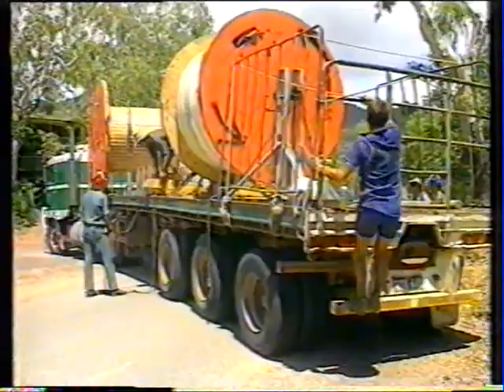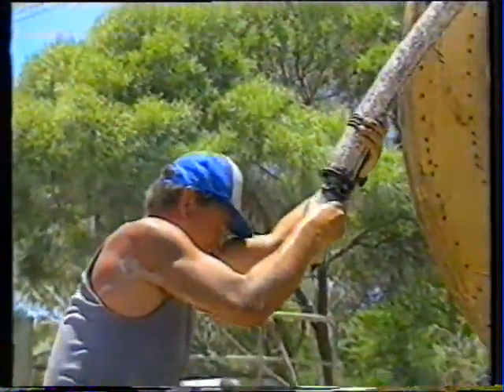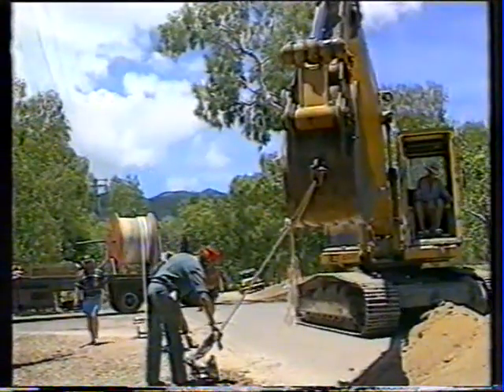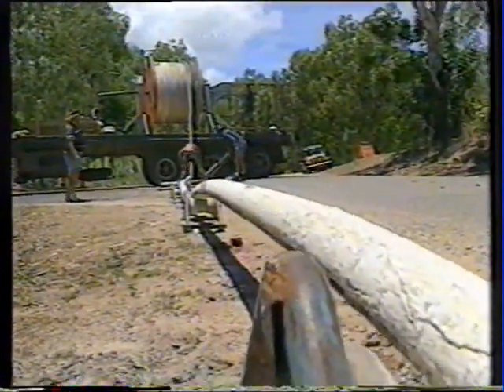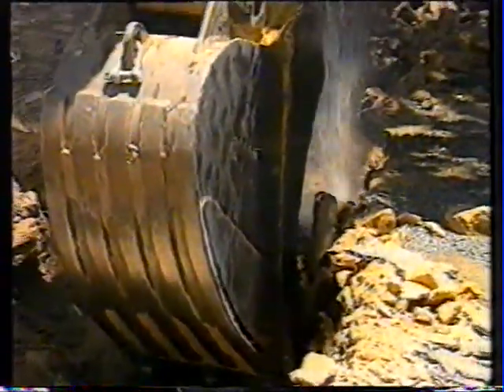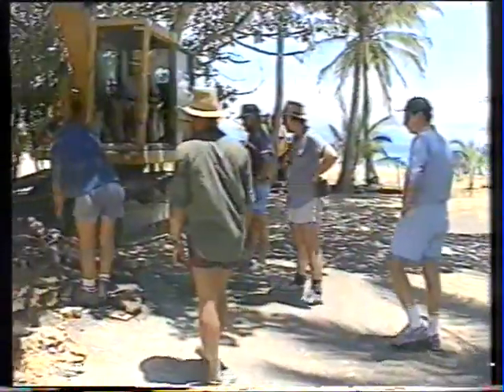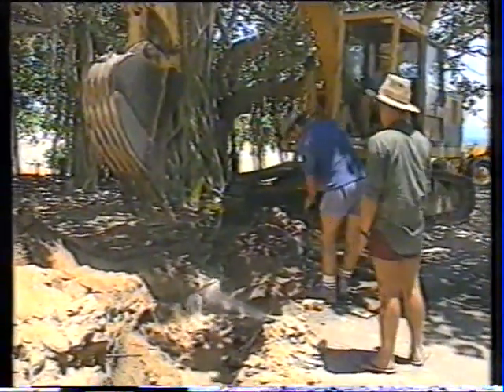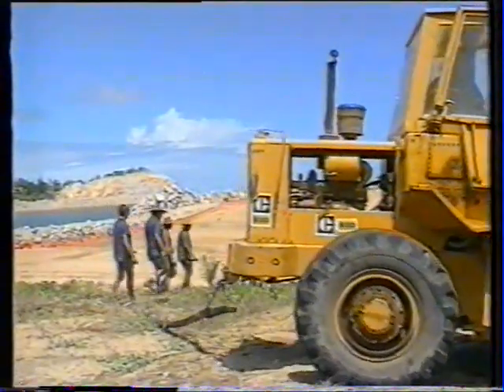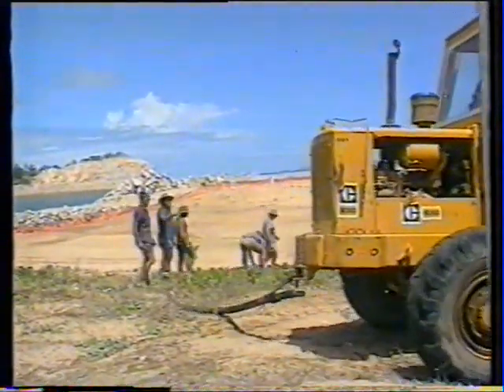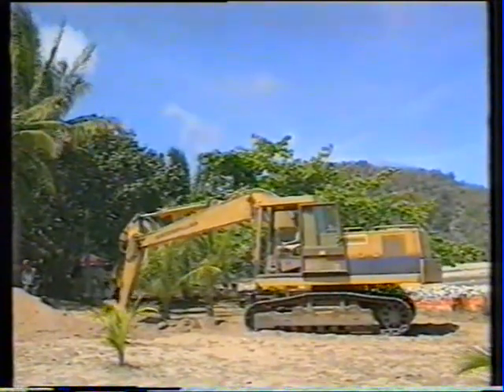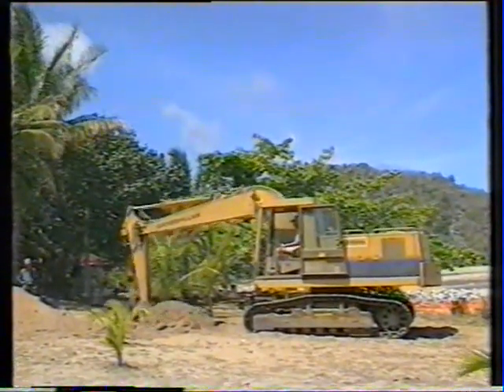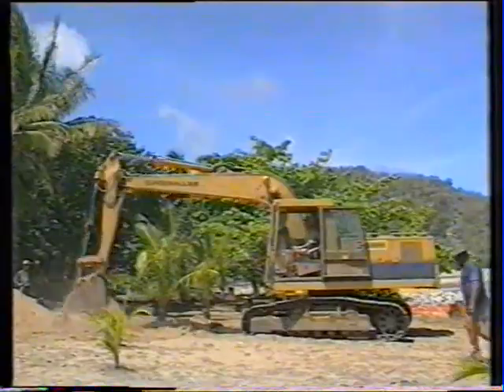This last section of the cable has come across by barge and will be installed from the semi-trailer using the excavator to start the cable pull. As with most operations of similar nature, there's bound to be some minor problems, and the excavator uncovers a small water main at the esplanade. This problem is soon rectified by local council staff who have been standing by. The remainder of the cable has been floated into the Nelly Bay site. Excavation down to the beach site continues throughout the morning.